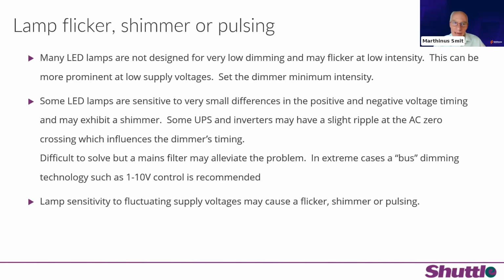Some LED lamps are very sensitive to small fluctuations in the difference between the positive curve and the negative curve when you start dimming. If we think back to the waveform of the leading and trailing edge dimmers, as I showed earlier, where the dimmer synchronizes on the red dots where the voltage crosses from positive to negative and then from negative to positive again, we do find that some UPSs and inverters have a very, very slight ripple. Otherwise, the waveforms are beautiful, but at the zero crossing, there's a slight ripple.